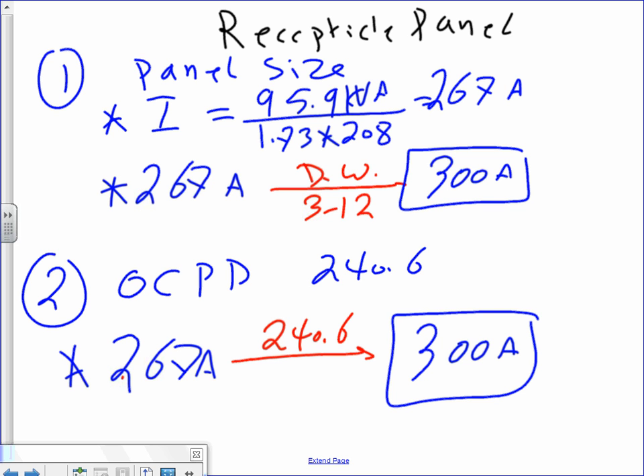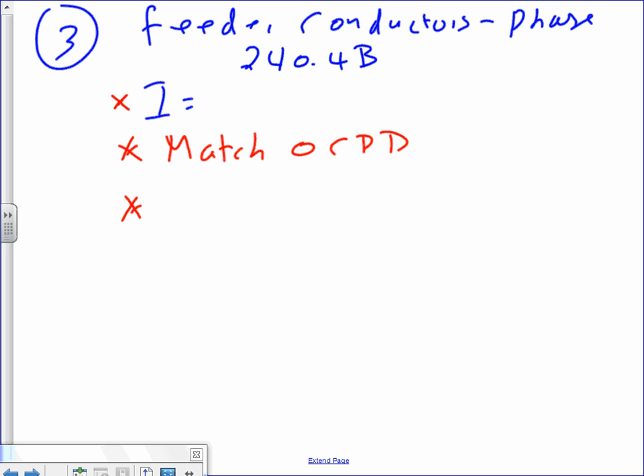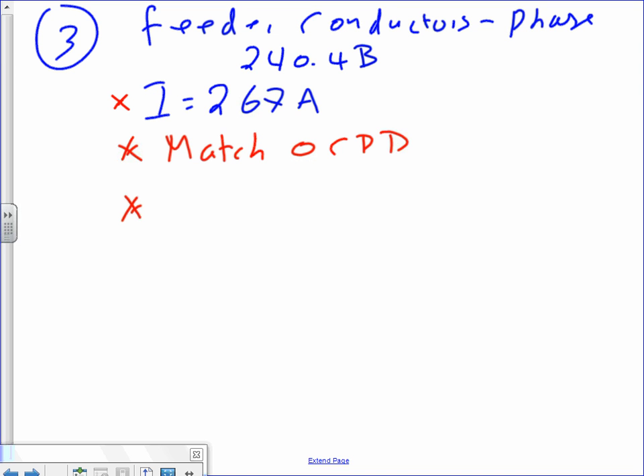Now we're going to repeat the same steps that we did for the service, guys, for all these. It's very easy, repetitive, basically. Cool. Yes, sir. Thumbs up. I told you, raise your hand. Feeder conductor. Number 3 is sizing the feeder. Okay, the current that I need to size for, guys, it was, where am I? So we are into the panel, okay. So 267 amps. I need to size a conductor for 267 amps.